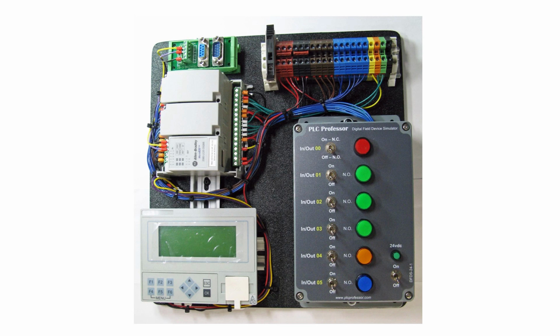Now, what you don't see underneath the 820, in other words, right below the 820, you see a yellow wire that comes around and then curls back towards the DIN rail, and you can see some ferrules back there that aren't connected. Those are the RS-232 connections if you want to connect up that HMI remote LCD to those 3 connections, the black, the yellow, and the purple, that go up to the top to that DIN rail mount breakout. So you can pull those 3 ferrules out, put these 3 in. Now you can use the USB connector on that little HMI to your PC, and it's passed through.